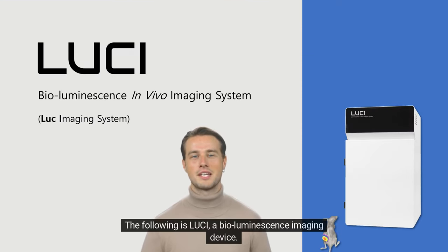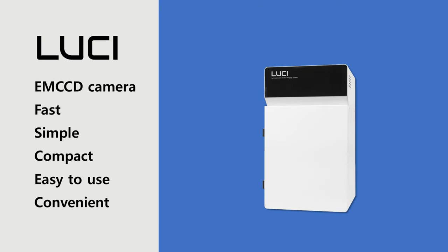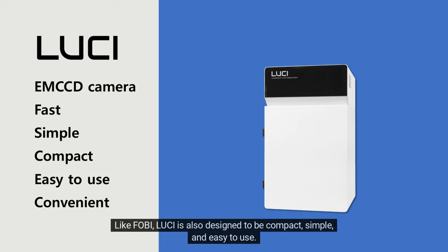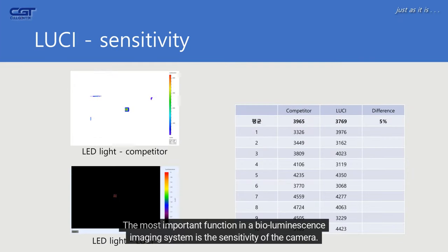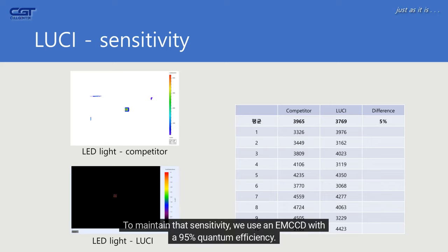The following is LUCI, a bioluminescence imaging device. Like FOBI, LUCI is also designed to be compact, simple, and easy to use. The most important function in a bioluminescence imaging system is the sensitivity of the camera. To maintain that sensitivity, we use an EMCCD with 95% quantum efficiency.